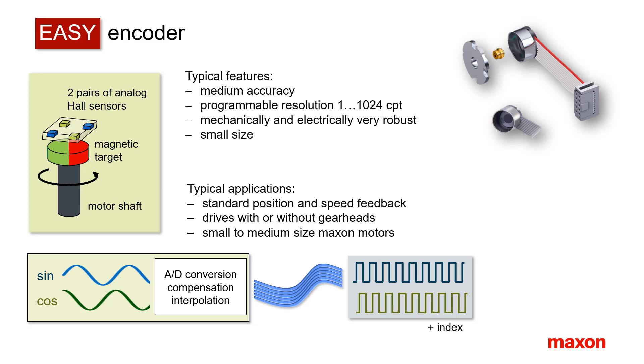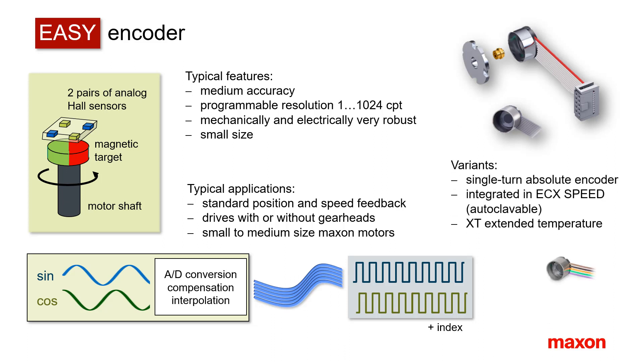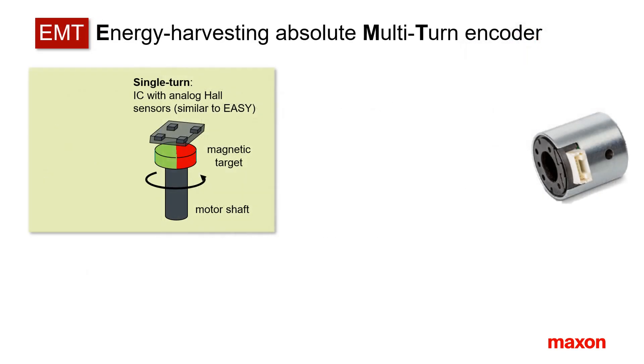The unique rotor position signal within one motor turn allows generating absolute encoder signals — that is the EASY absolute single-turn encoder. While the EASY absolute encoder can only give absolute position feedback within one turn, the EMT is also capable of keeping track of the number of turns.